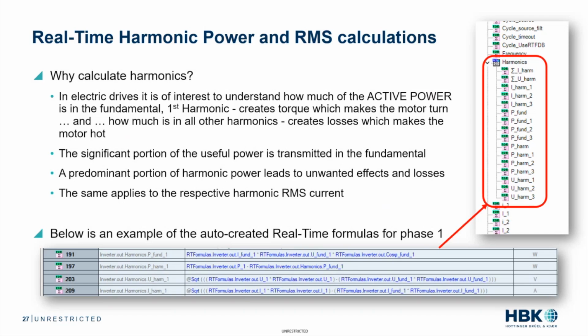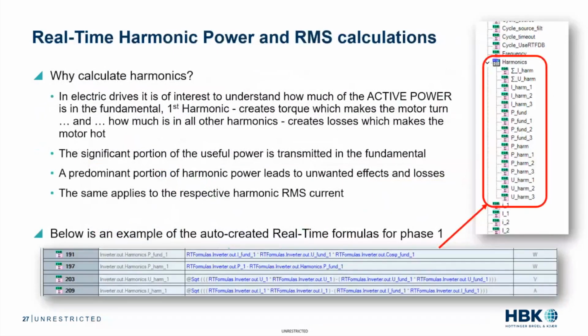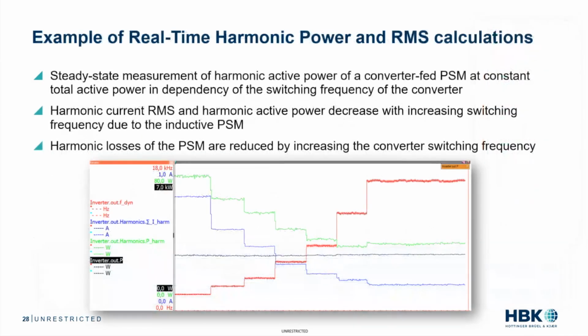Here you see just an example of some of the equations that are automatically generated, and they're actually performed in real time. These are for phase 1. And you can see the list on the right for the calculations that are performed for current harmonics, for phases 1, 2, and 3, and also for power, the fundamental, and the harmonics, and also the voltage harmonics for phases 1, 2, and 3, etc. So these basically become very valuable. And how valuable, you may ask?